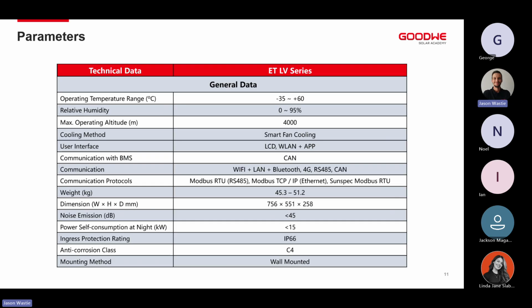We go to the general data. So the general data on the system, for the ETLV series, you'll see there is smart fan cooling. So there are built-in fans on the inverter. These built-in fans do not run permanently. They only run when the inverter reaches a certain temperature. So when the temperature on the internal side of the inverter gets too hot, the heatsink obviously will do as best as it can. Thereafter, the smart fan cooling will kick in and we'll be able to cool that inverter down and keep it running.